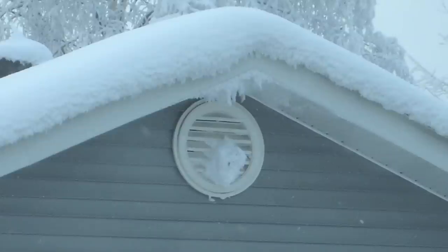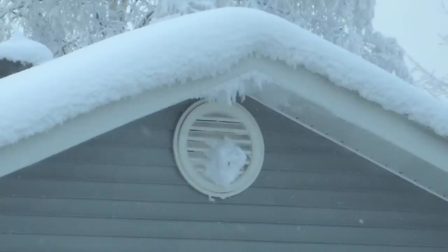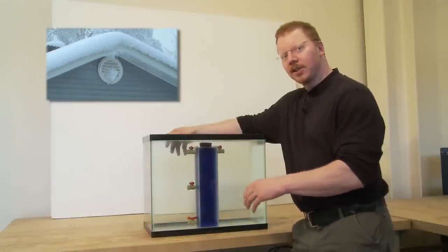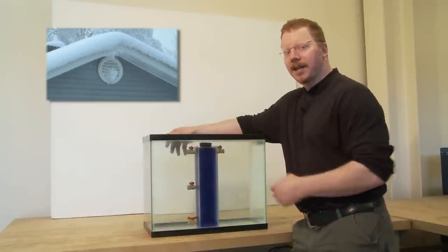We've demonstrated with stack effect that hot buoyant air rises and leaks out up at the top. If you've ever seen an attic vent in the wintertime with a lot of frost around the outside, that's a pretty sure sign that you've got some water vapor traveling via air leakage and stack effect up into your attic. If that water vapor stays up there long enough and becomes trapped, you could have some other problems. But that's not the only issue.